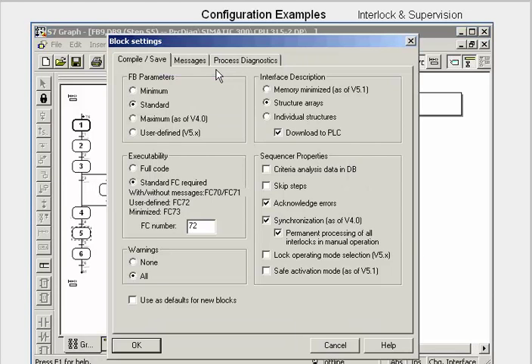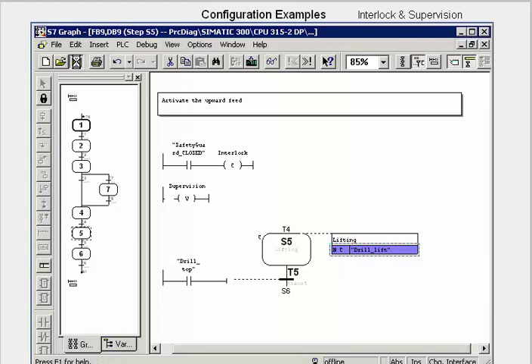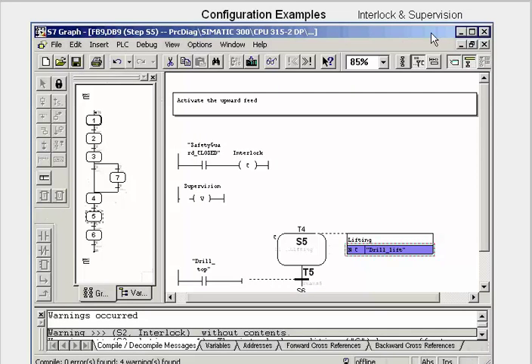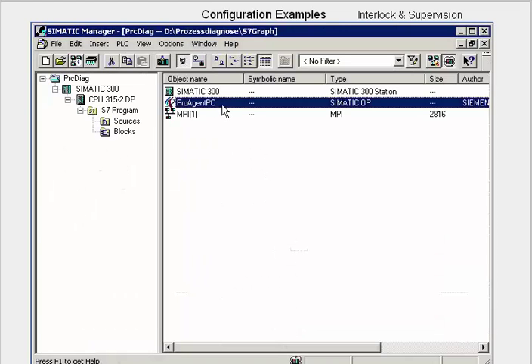Now we have to make the following general settings for S7 graph. We open the block settings dialog and in the messages tab, we activate display acknowledgement on the HMI device, both for interlock and for supervision. We acknowledge the dialog and then save the sequencer, load it into the CPU, and close the editor.